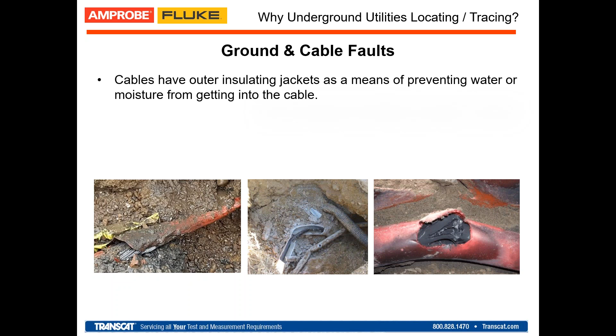One important thing we've seen is that the majority of cable faults our users are buying our equipment to find—degradation of the insulation—happens mostly because of soil conditions combined with cable quality. Where there's a high relative humidity coefficient in the soil combined with high acidity, that's where we see more degradation of the cable insulation.